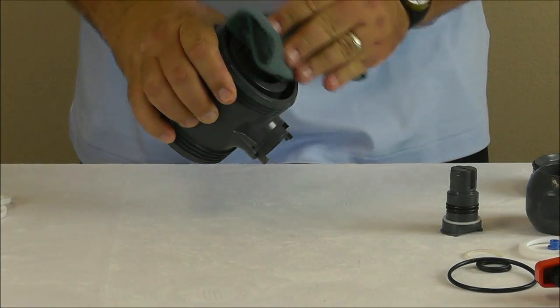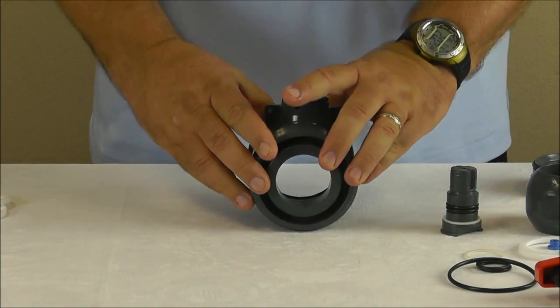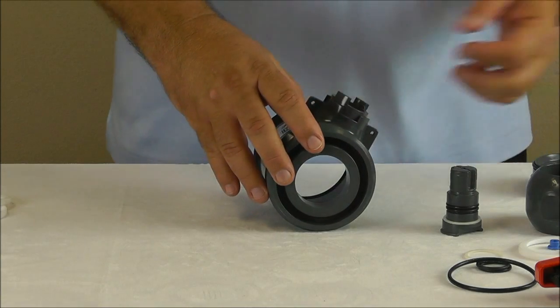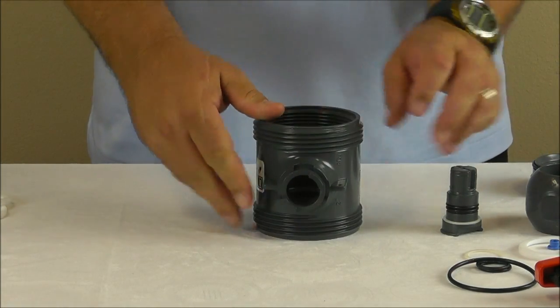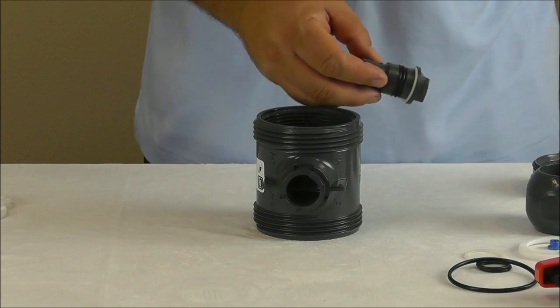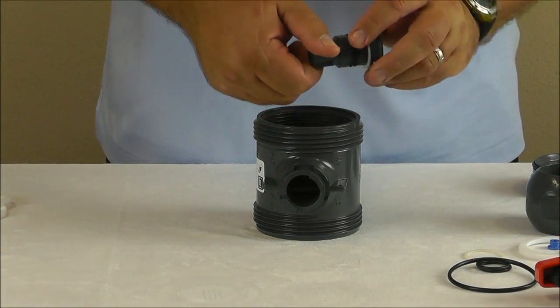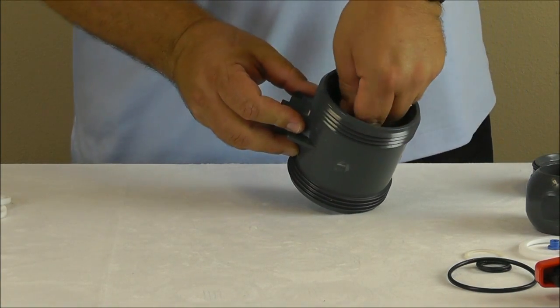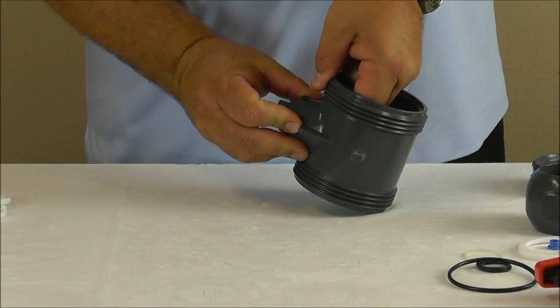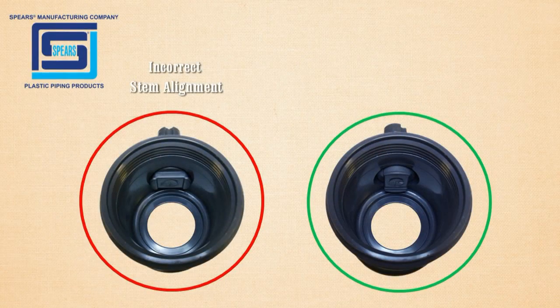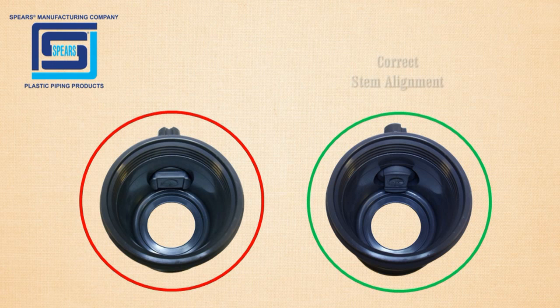Clean the valve body and lubricate the stem port and stem o-rings. Reinstall the stem from the inside of the valve body. Make sure the stem is properly aligned to reinsert the ball.